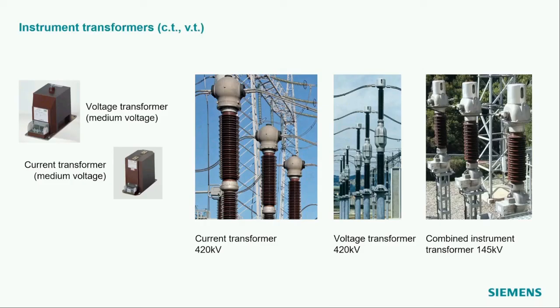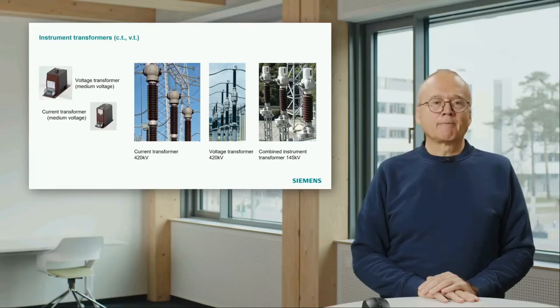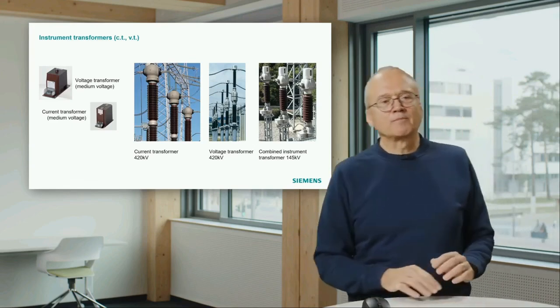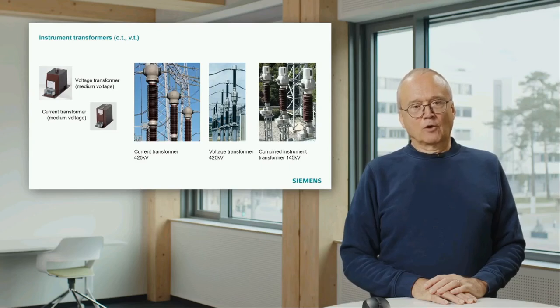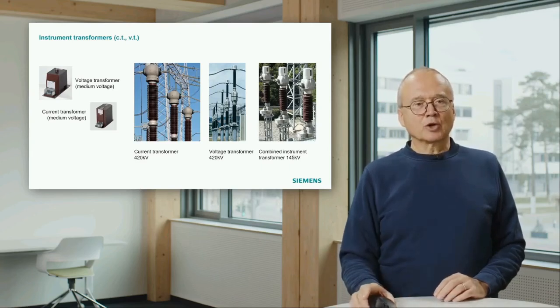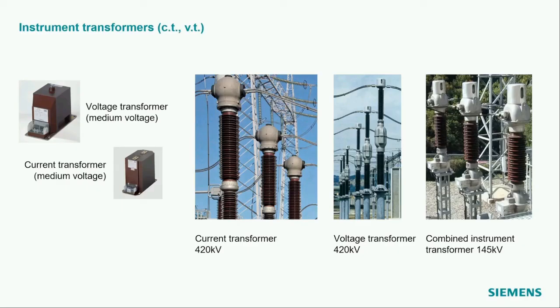Let's also have a short look at the instrument transformers, just to show a few examples. On the left-hand side, you see a voltage transformer and a current transformer for medium voltage. You see here the connection points for the voltage and also for the current. That means the current flows through the current transformer this way. The primary current in the line is connected to this one. And our protection relay is then connected here in the bottom at these terminals, where we see the transformed voltage and also the transformed current.